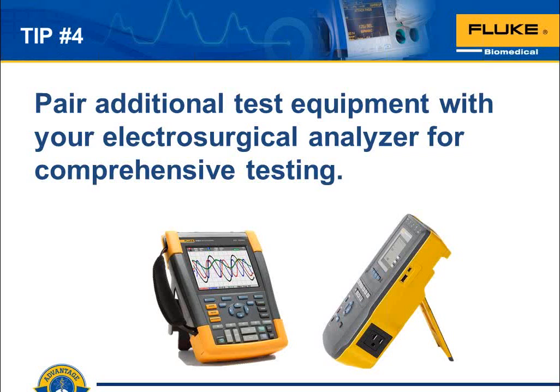So we're going to do all of that. In addition, you should use an oscilloscope. A medical oscilloscope should be a portable one, so it's easy to carry around, and to look at the actual wave shape of the output energy from the ESU. The waveform output can be compared to pictures that are usually found in the electrosurgery unit service manual, and those waveforms may be found in the calibration part of the procedure for cal adjustment.